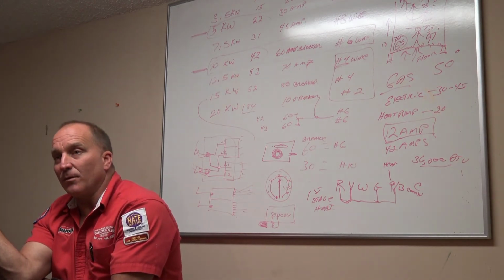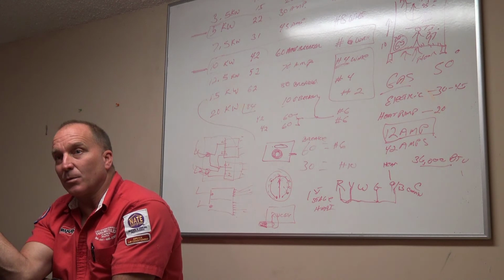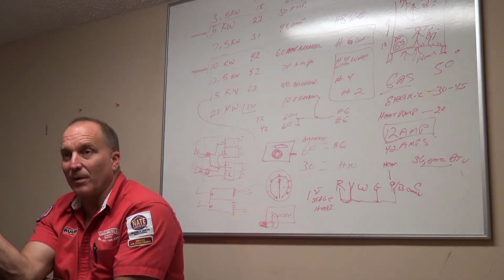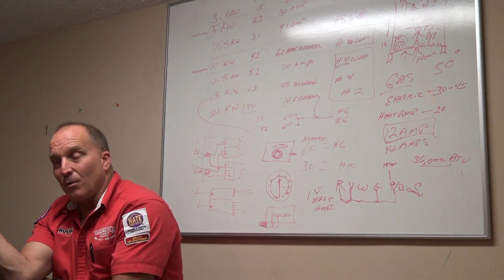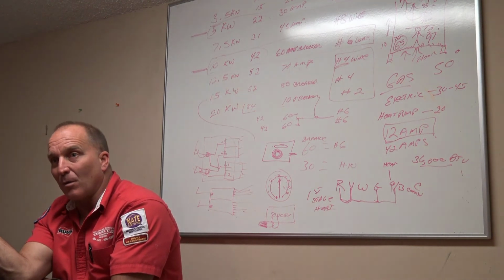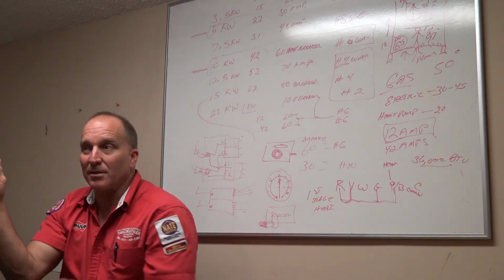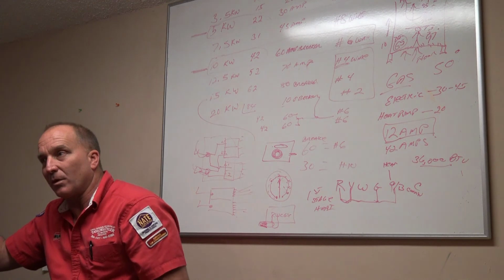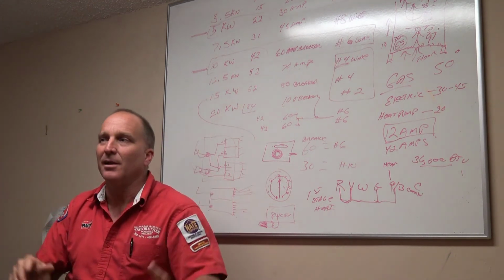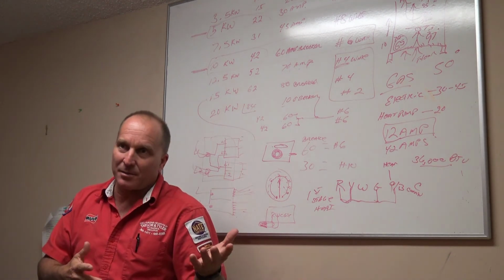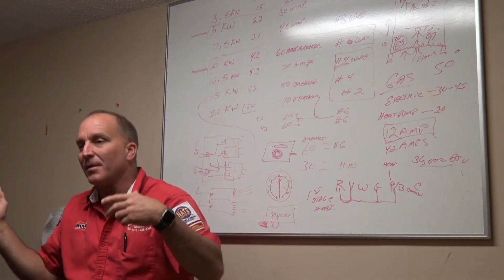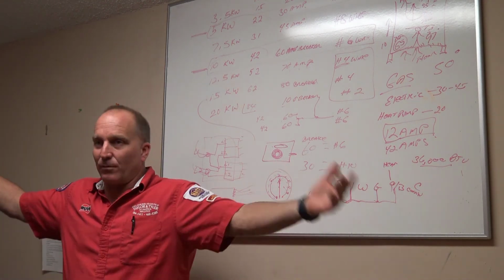And I can also prove that Cousin Bill didn't lower the blower speed because it was a 5-ton furnace and it's really a 3.5-ton condenser, and you were blowing 2,000 CFMs of airflow. Now we're blowing 1,400 CFMs. So Cousin Bill overcharged the system with the 5-ton airflow, and I reduced it, and I let refrigerant out of the system. I recovered the refrigerant out of the system, and Cousin Bill had it running on 5 tons.